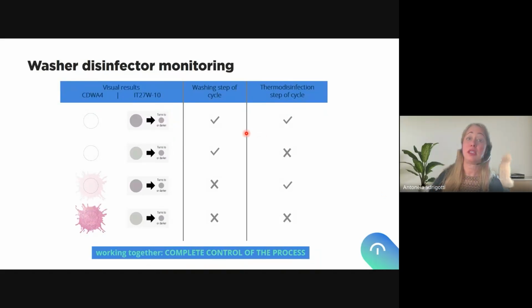So in the end, as I have anticipated, washer disinfector monitoring will be perfectly controlled when we have two different indicators for monitoring two different steps. A physical removal of organic residues with a specific indicator that will show this elimination or removal of organic residues, and the thermal disinfection indicator that will specifically monitor the time and temperature that makes sure that I will reach the right disinfection level or inactivation of microorganisms. Two different processes happening inside one full cycle.